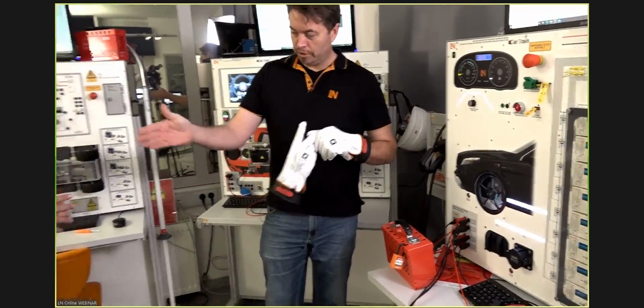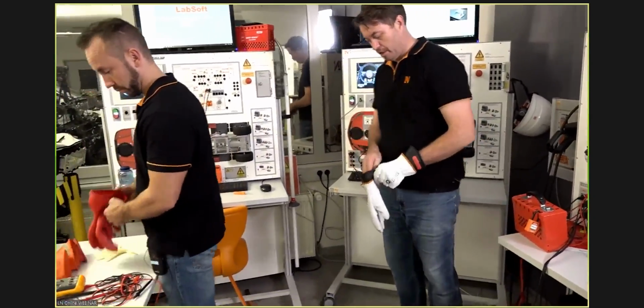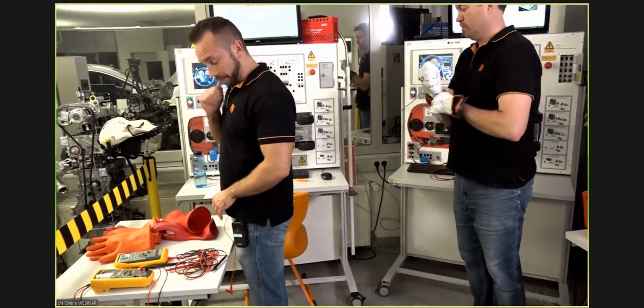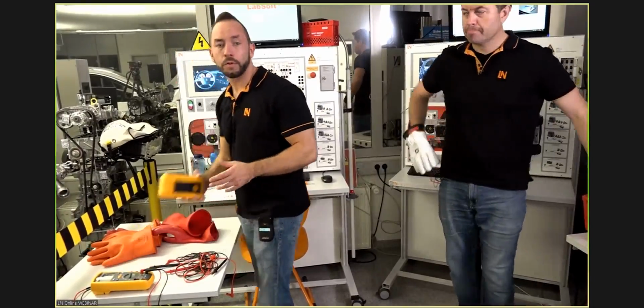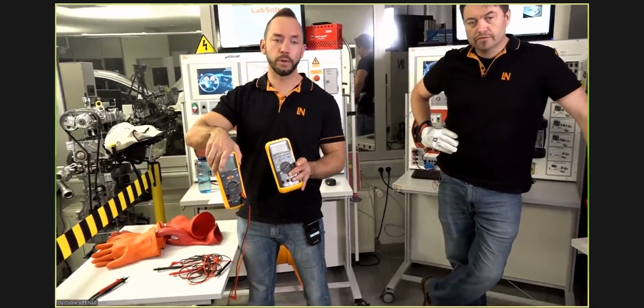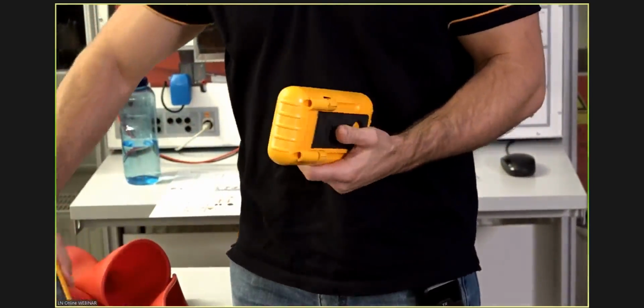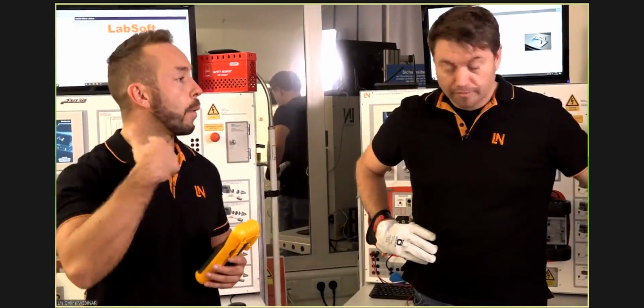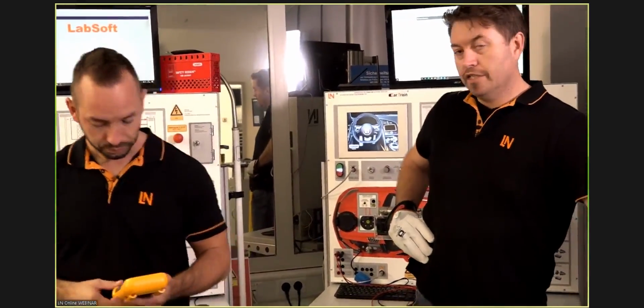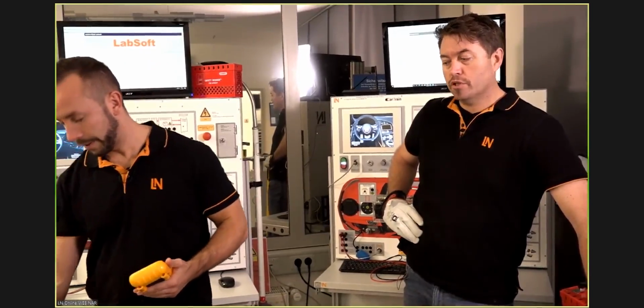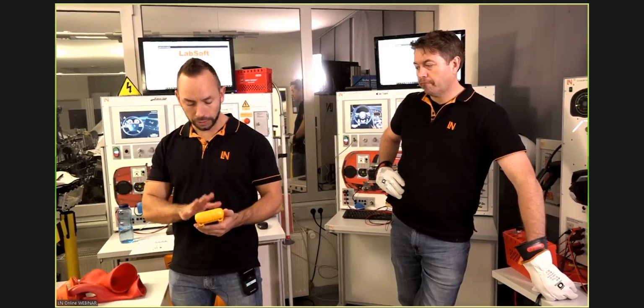Christian, can you please pass me a measuring device and explain the difference between them? Both are Fluke measuring equipment, they look pretty much the same, but they are absolutely different. When we're talking about insulation measurement, we want to measure really high resistance, not kilo ohms but very high levels of mega ohms. Another name for this insulation test is meg ohm meter, or Megger, as some people call it. So what's important first is the measurement area, you need to look at these measurement tools.